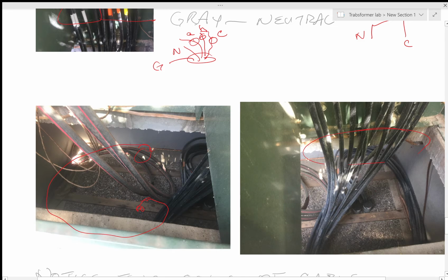They have an ABC phase in this conduit. They have an ABC phase in that conduit, and right behind here they have another ABC phase. And in each one of those they have 4 wires and a ground. Here's your ground wire right there. So they have an A, a B, a C phase, and a neutral and a ground wire in each one of those 3 conduits. And that way they spread the wealth. The magnetic fields cancel out and the currents cancel out. Now when I get inside, I got currents, but that's the way it is.